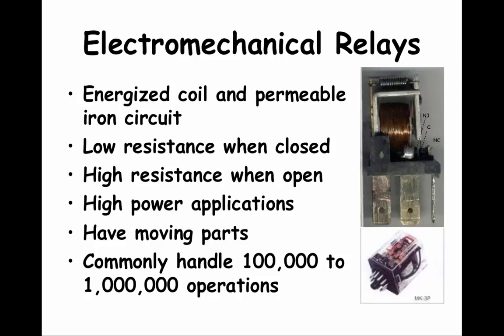When the circuit is closed, the armature moves to close the circuit. The two sides physically touch, so the resistance to electrical energy flow is very low. When the circuit is opened, the armature moves to create a gap in the circuit, and electrical power cannot flow — the resistance to flow is very high. These electromechanical relays are used for high power applications, like 10 horsepower motors. The low resistance when closed and the high resistance when opened are big advantages, but a disadvantage is that moving parts can wear out over time. Electromechanical relays can open and close in the range of 100,000 to 1 million times.